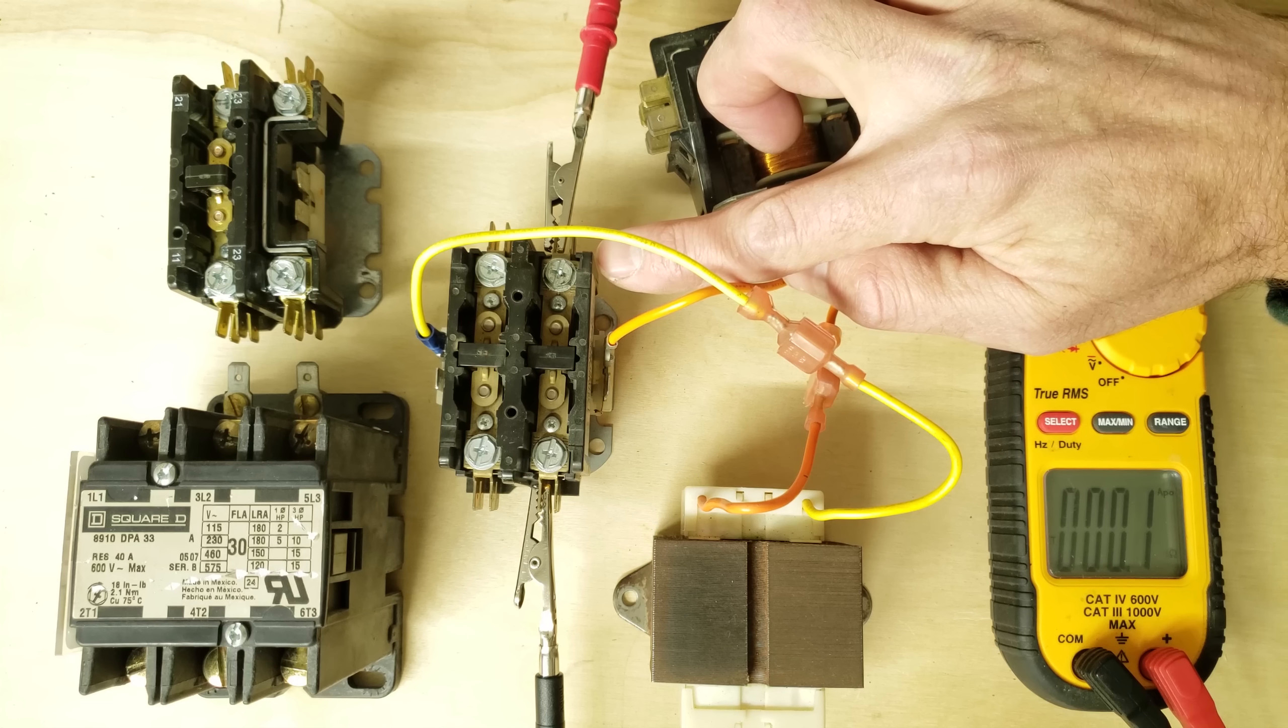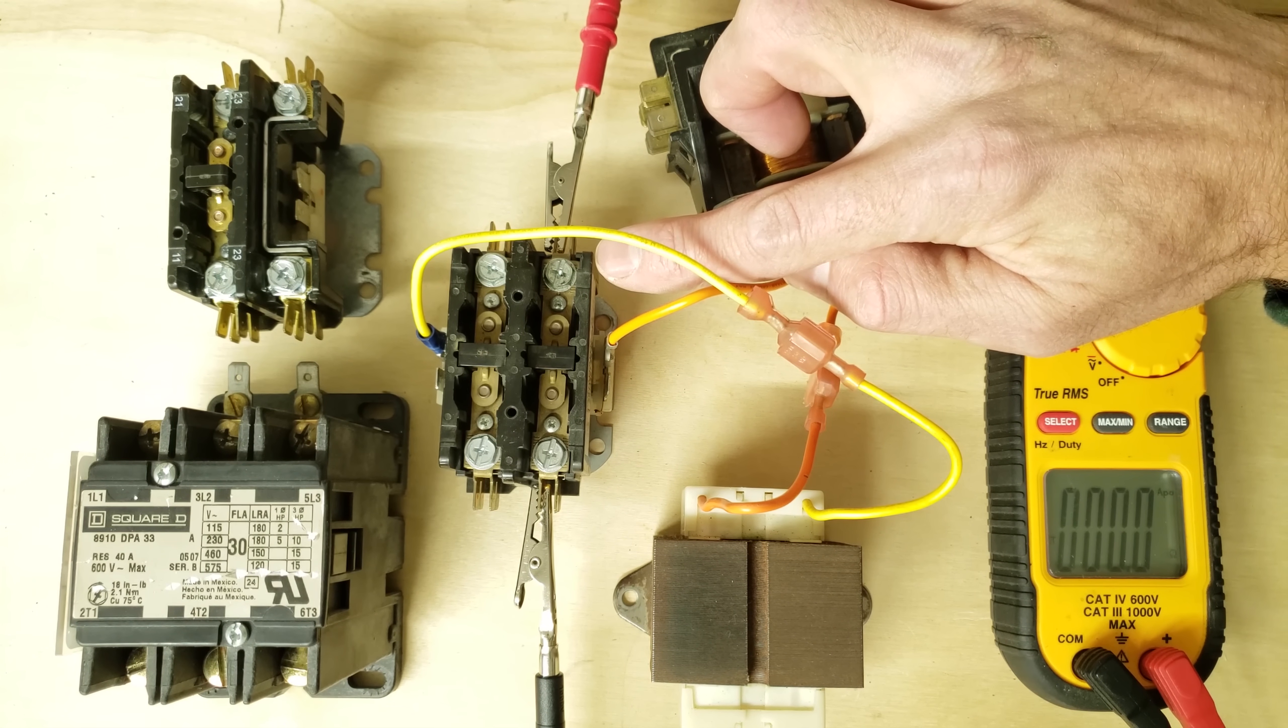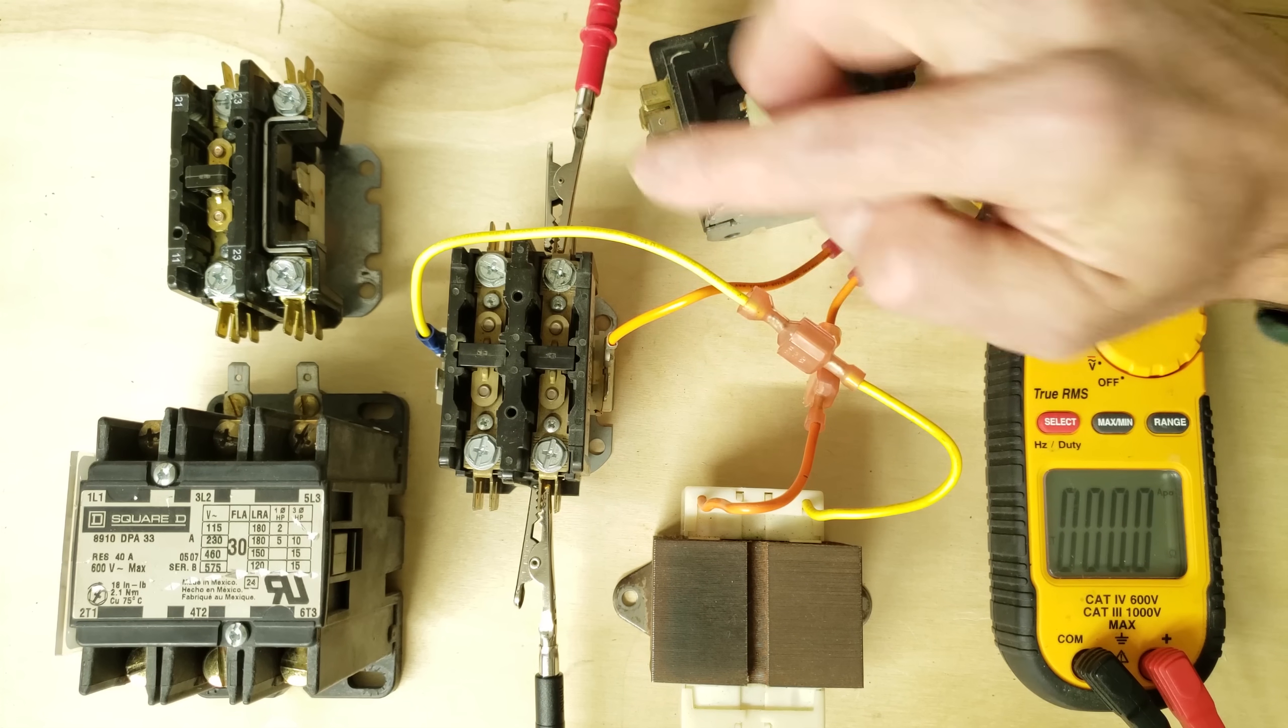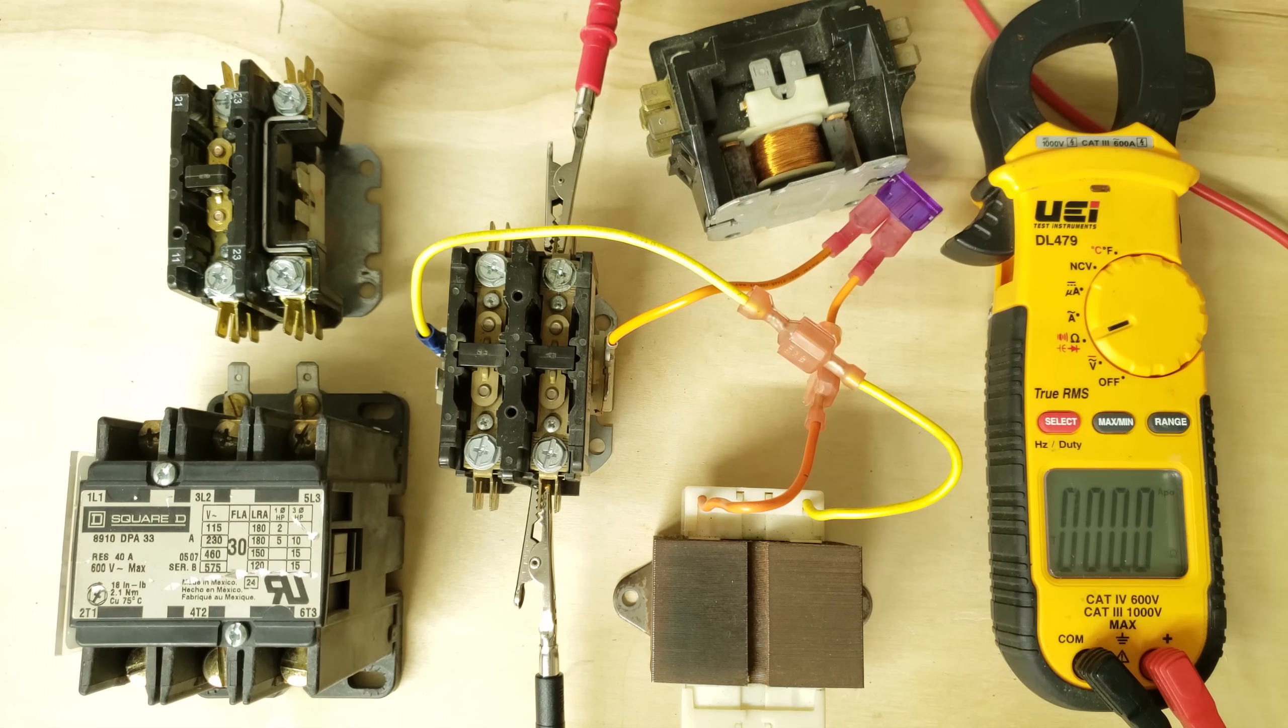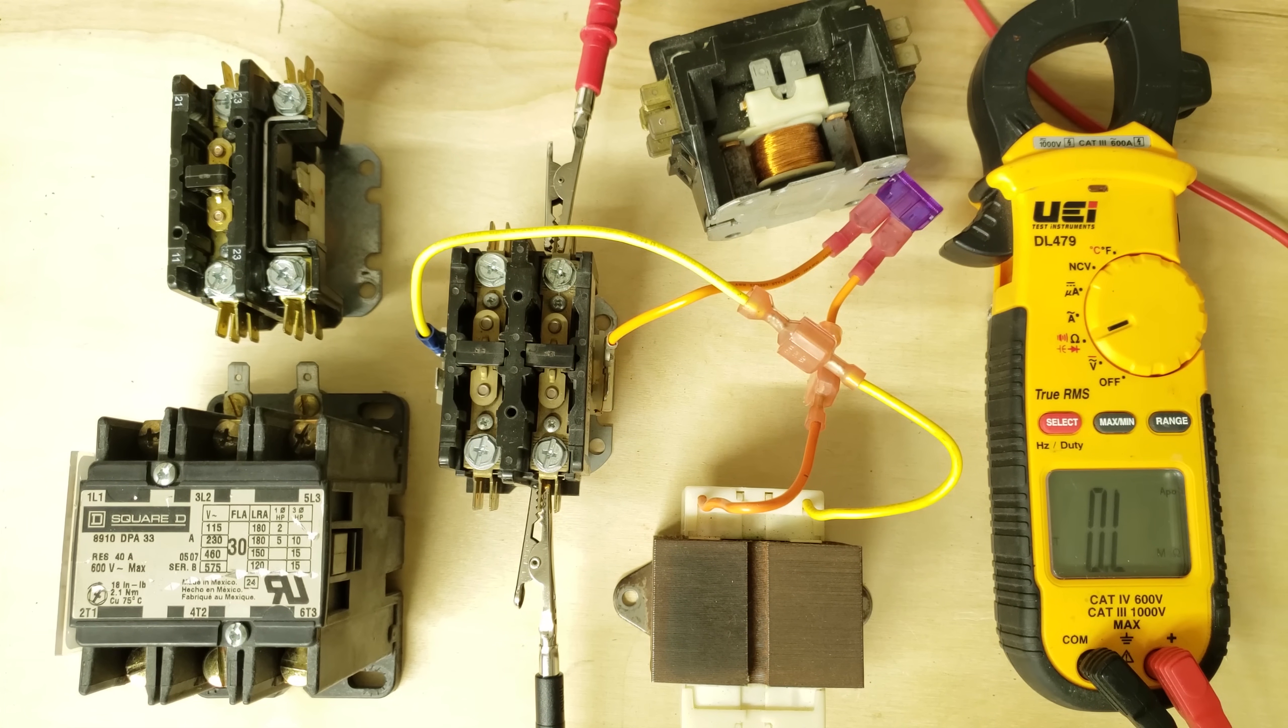Now we have 24 volts powering the coil which is an electrical magnet sucking down the contacts. We have our one probe here and our other probe here and we're reading on our multimeter 0.0 ohms of resistance. So that means the contacts are closed, they're connected. Now we'll disconnect our 24 volt power and we're reading OL which means open line. So now we're not connected. That's how the contactor works.